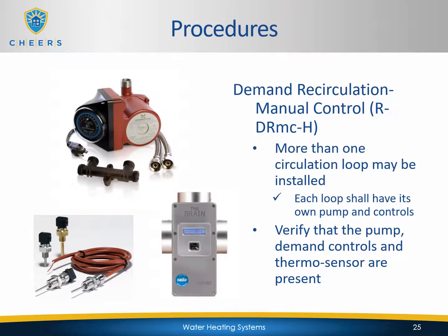So there may be more than one circulation loop, so you're not limited to one. That's the most common, is to have just a single loop. But if you're in a very large house and you have multiple water heaters, you may have multiple loops present within the house. Each loop must have its own pump and controls, and then you will be verifying that the pump, demand controls, and thermosensor are present. So the pump and the thermosensor are generally going to be located very close to the water heater. The thermal controls or the demand controls themselves are going to be located throughout the home at various places, and we'll look at where they're required. So part of your inspection is to go through and make sure that these items are installed.